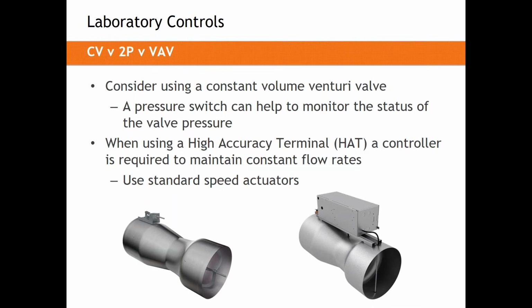So in an operating room or an isolation room or even a compounding pharmacy, if you can use standard speed actuation, you should. The motor costs a bit less, and it's easier to set up and tune and can be more accurate. An operating room, for example, or even an isolation room, might go from a minimum set point to a maximum in setback modes and occupied modes. That change does not need to happen in the matter of a few seconds. It can take maybe a minute. The room is still changing over quick enough for its usage, and we don't need to incur the cost and complexity of high-speed actuators for that. Anytime you increase the speed of a measurement and control system, you increase its complexity and increase the cost to set it up and tune it.